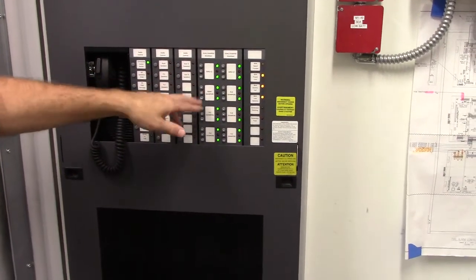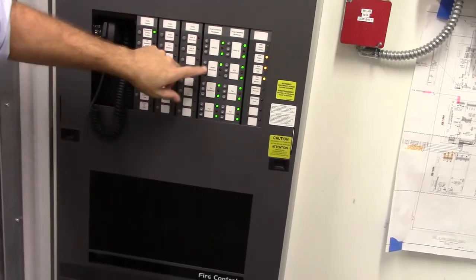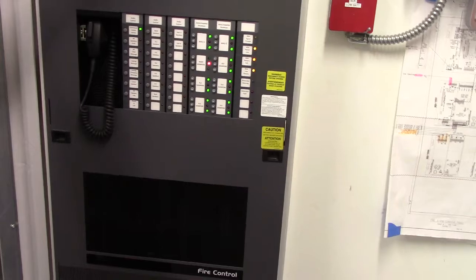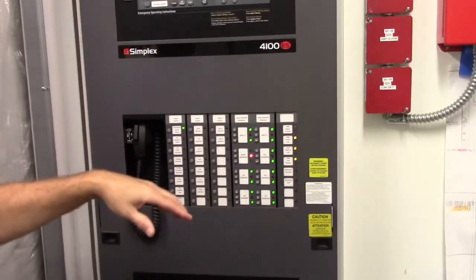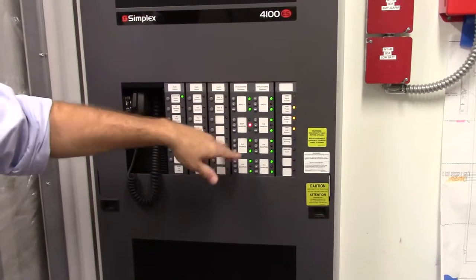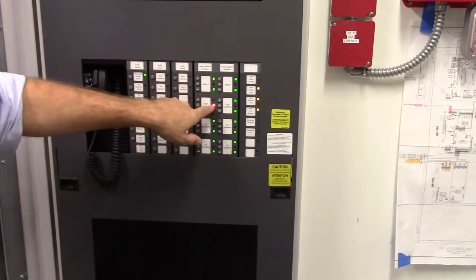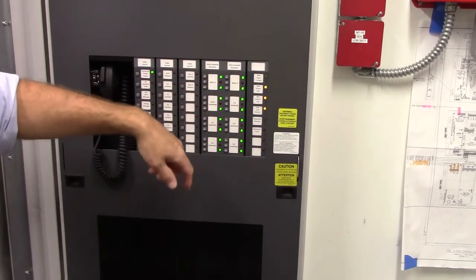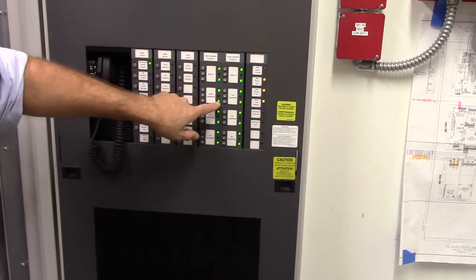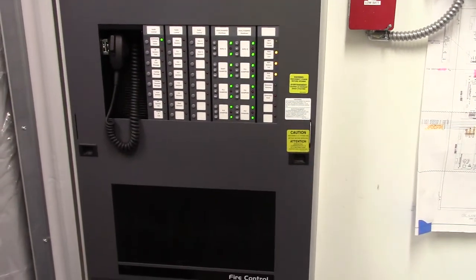If you do manually turn one of these on, you'll get an override. You'll get an override trouble, showing that it's no longer in auto. If the system's normal, when you go to put it back, you want to put it back in the state you want it to stay in. So right now this is shutting off all your dampers. So we're going to turn the air back onto that floor, and then you hit automatic. And as long as you've got this bottom light, the system's got control of those dampers.